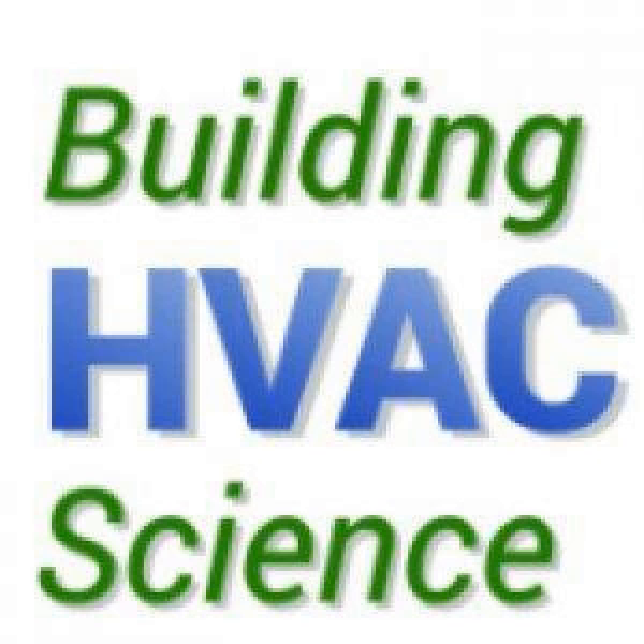His furnace, his HVAC return comes down the stairs through the open door to the basement, and it goes through the mechanical room doorway with no door and gets sucked into the fan. He's allowed for lots of airflow with very little resistance and has lots of dilution air to make it work right and not feel bad to consumers, because you've got to distribute that cold air. You have to get it away from the heat pump. Otherwise, you'll contaminate the source air with cold air, and that's not what you want.